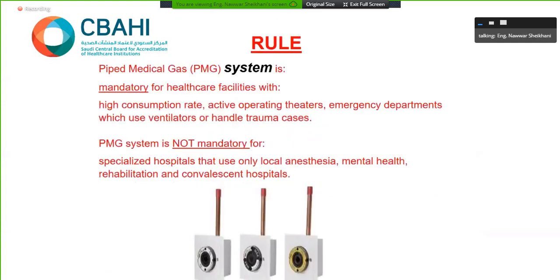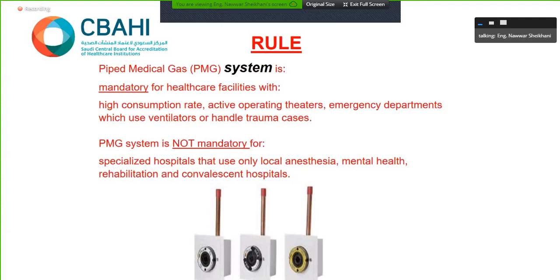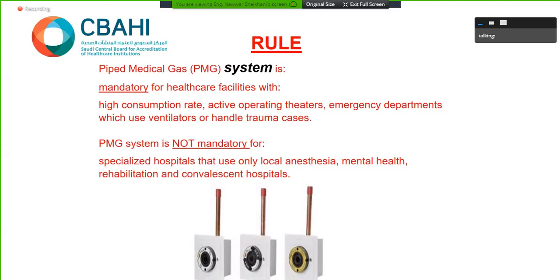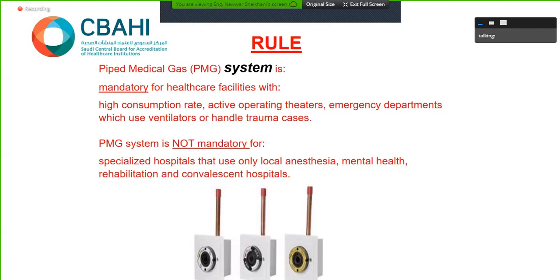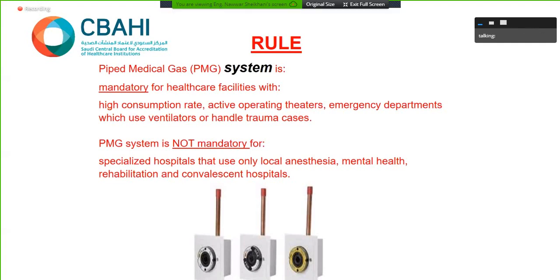Before starting, there is a rule we have agreed with our colleagues in CBAHI, MOH, Civil Defense, and Saudi FDA. There was a representative. We have agreed on this rule where we have to see a system, not cylinders. It is mandatory for healthcare where we have a high consumption rate, active operation rooms or theaters, emergency departments, trauma rooms, ventilators, etc. It's not mandatory for specialized hospitals like eye hospitals, mental health or convalescent hospitals.